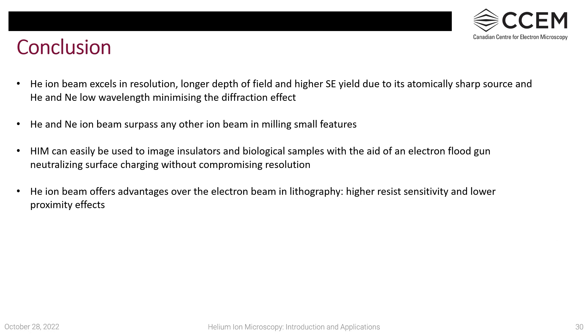To conclude: helium ion beam excels in resolution, longer depth of field, and higher secondary electron yield due to its atomically sharp source. Helium and neon have low wavelength compared to electrons, minimizing diffraction effects. Helium and neon ion beams surpass other ion beams for milling small features. Helium can image insulators and biological samples without coatings using the electron flood gun, and helium ion beam lithography offers advantages over electron beam lithography including higher resist sensitivity and minimal proximity effects.